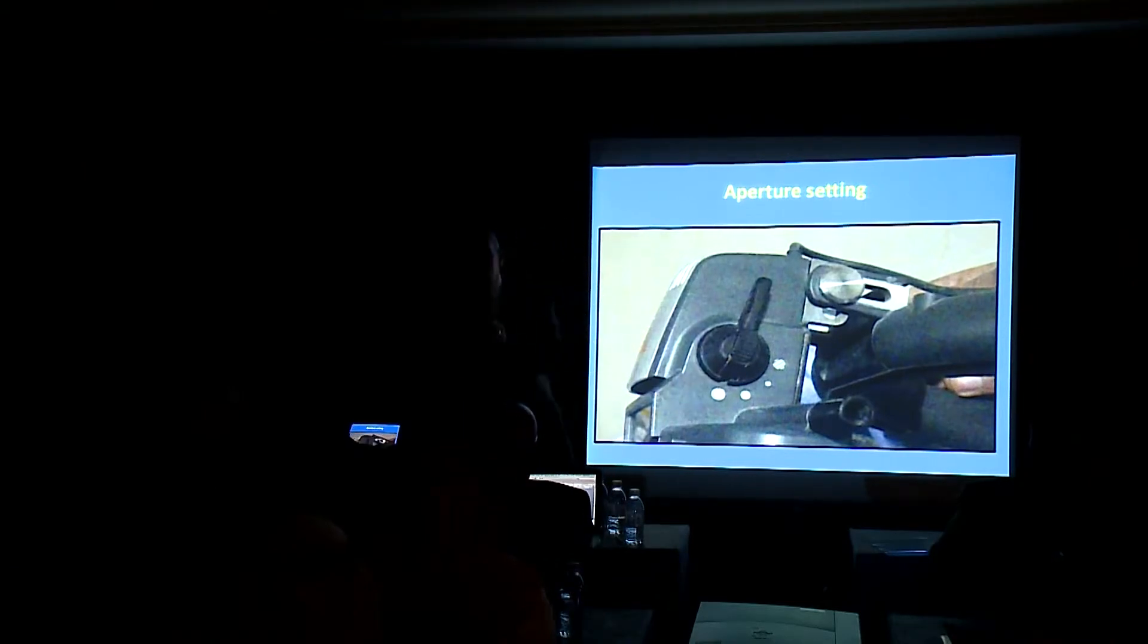Again, aperture setting. You have a knob to adjust the aperture because sometimes you get a narrow pupil. You put the narrow beam so that the light goes through the pupil and both your binocular eyes go through the pupil. Otherwise, you get a non-stereoscopic vision.